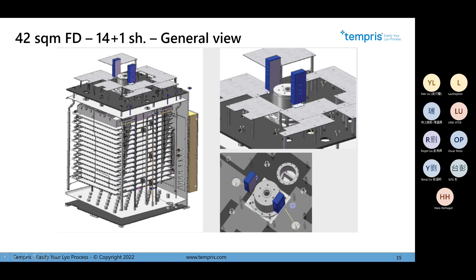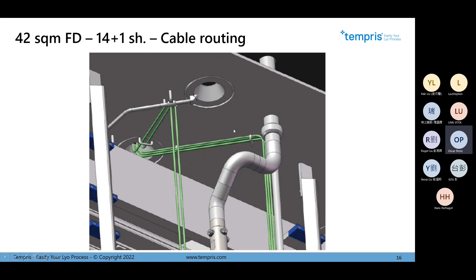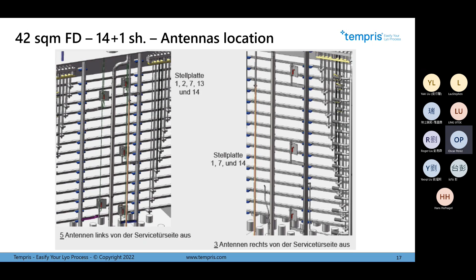Here we can see the guidance. This is a new freeze dryer, so they built some guidance for the cables also, coming from the flange and going to the different rods or holders for the antennas. So we can see here we place on this side antennas in shelf 1, 2, 7, 13, and 14, each on different mini rods, let's say, attached to the existing frame parts of the freeze dryer. And on the opposite side of the freeze dryer, we have placed three additional antennas in shelf 1, 7, and 14.